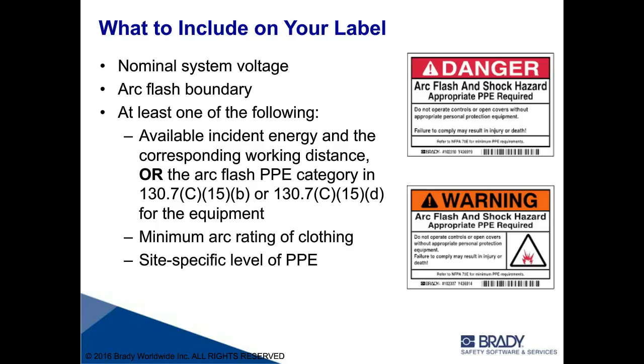So that arc flash boundary is going to be directly related to how severe that explosion is going to be. The greater the explosion, the more distance that explosion is going to travel out of that piece of equipment. And at some point, it dissipates and gets down to a level of 1.2 calories per centimeter squared, and that's where that arc flash boundary is defined. People outside that arc flash boundary are still potentially going to be exposed to some incident energy, but the levels at that distance are going to cause something less severe than a second-degree burn, so it's not a high level of risk.